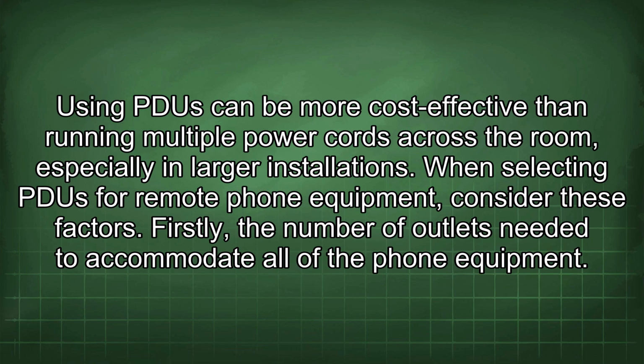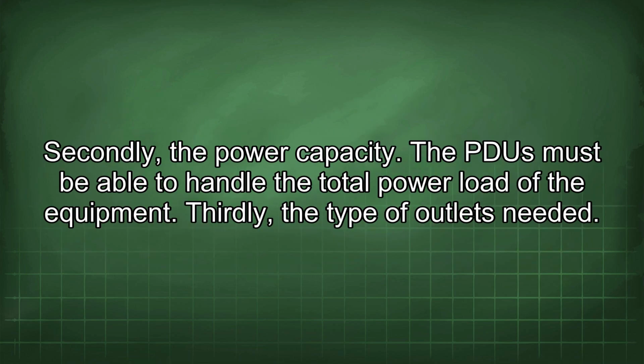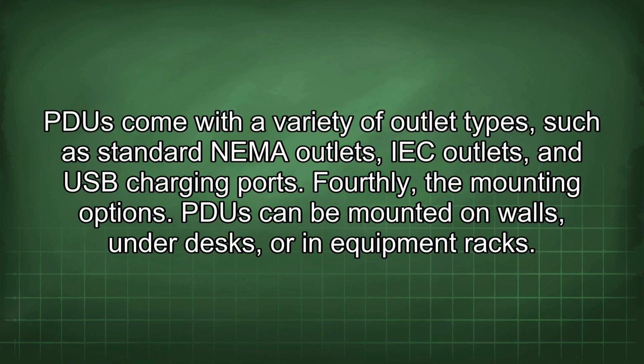When selecting a PDU for remote phone equipment, consider these factors. Firstly, the number of outlets needed to accommodate all the phone equipment. Secondly, the power capacity - the PDU must be able to handle the total power load of the equipment. Thirdly, the type of outlets needed, such as standard NEMA outlets, IEC outlets, and USB charging ports. Fourthly, the mounting options - PDUs can be mounted on walls, under desks, or in equipment racks.